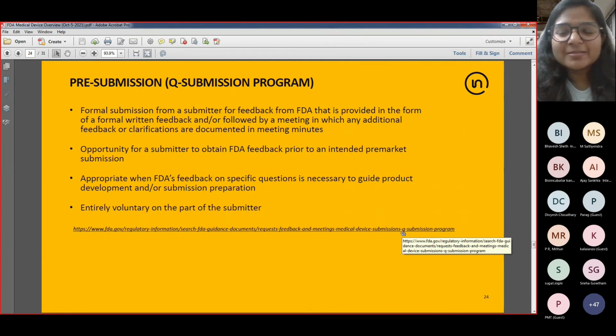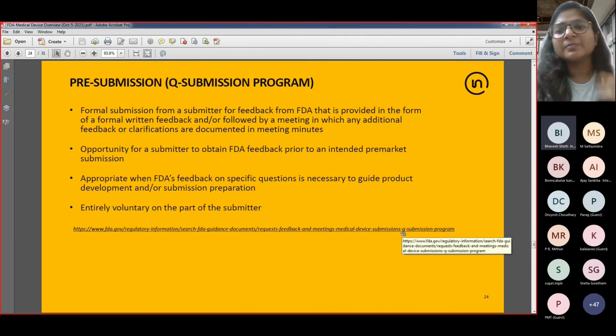Where to get an online submission form? FDA register, any URL? This is from Mr. Arun Kumar. Yes, there is a link on the FDA website where they've given all the forms, including the 510K forms and any other forms. Now, bear in mind that for any of these submissions that you decide to make, there is a detailed guidance provided by FDA on how to prepare a 510K and how to prepare a De Novo. When you read those guidance documents, you'll find references to some specific forms, and those forms are provided on the FDA website.